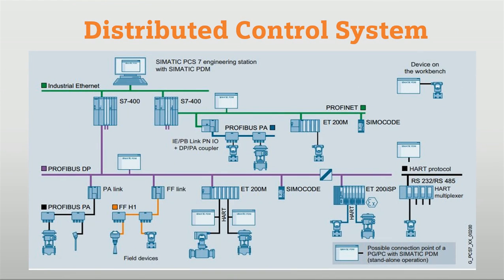First, we will see the architecture of the DCS system. At the top side we have engineering stations. From the engineering stations we can generate new projects, make programming for the automation station, and hardware configurations can be done. This engineering station has dedicated software for parameterization, programming, and documentation. The engineering station and automation station are connected with the plant bus, and for plant bus we mostly use Profinet or industrial Ethernet.